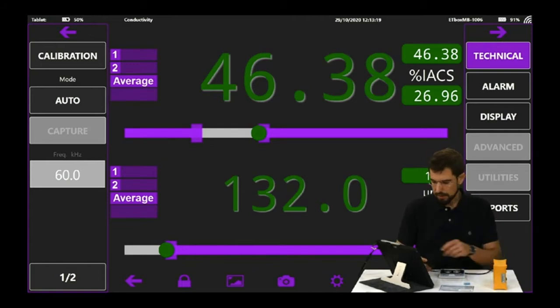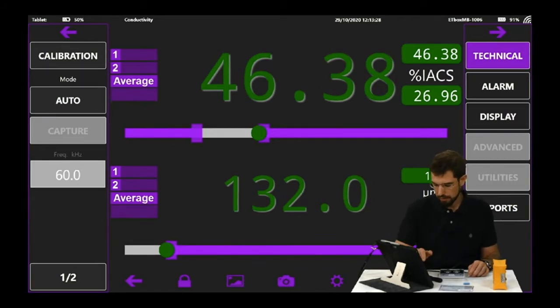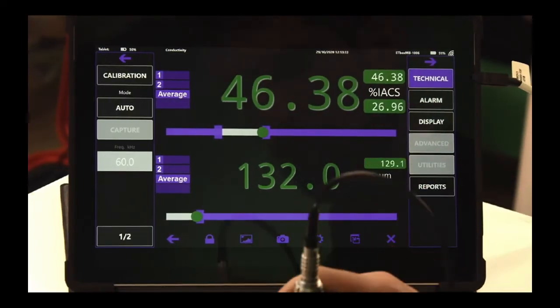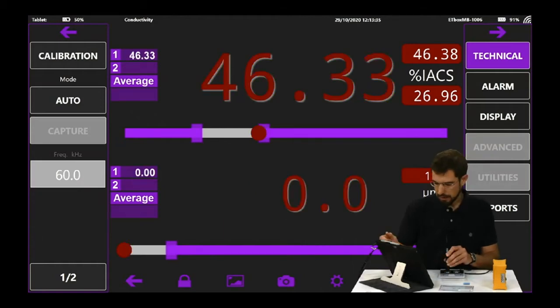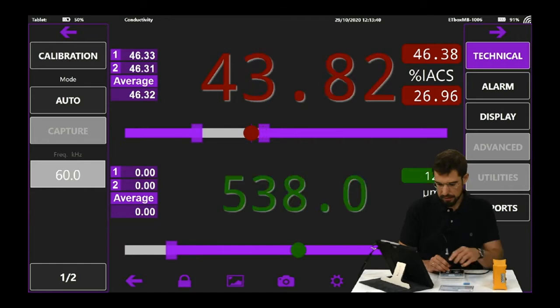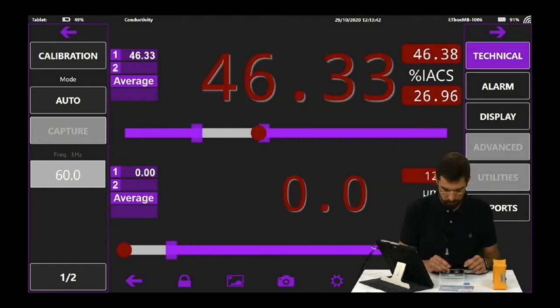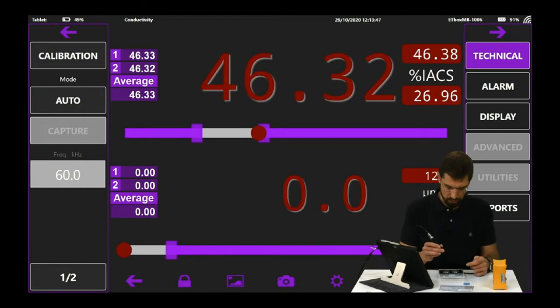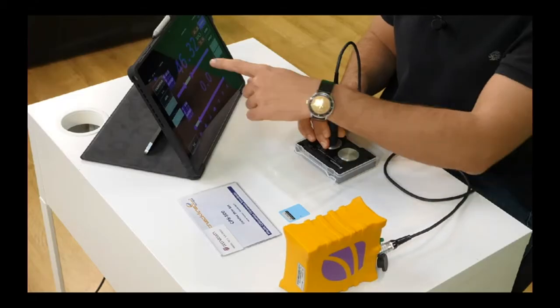Now we can see on the screen some menus and submenus that look more familiar to us. In the upper middle section of the screen, we can see the conductivity measure, and in the lower part, the thickness measure. On the Technical tab, we find a description of a series of parameters we can choose. That would be the acquisition mode, which is in this case automatic, and the software identifies if the probe is on the air or if it's laid on the material. When the measurement is fixed, it goes green.